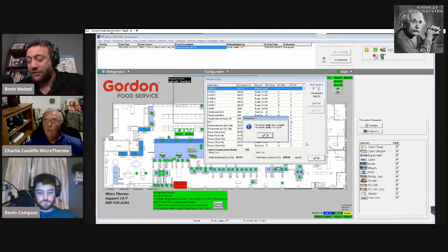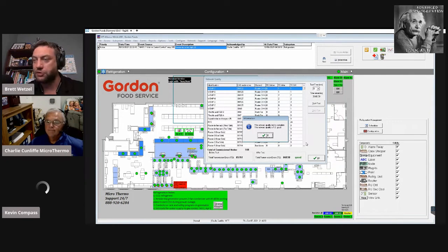So I've seen a lot of times where it'll say that it's supposed to have a 240 transformer, but maybe they messed up and it's supposed to be 208. Well, basically that's going to throw your voltage off. Especially most of the time you'll see this in the peak of summer, because the hotter it gets outside, more people are turning on the air conditioning. We're just putting draw on the voltage on the grid, and basically your voltage is all the way in the toilet, causing any of your controls or anything to malfunction.